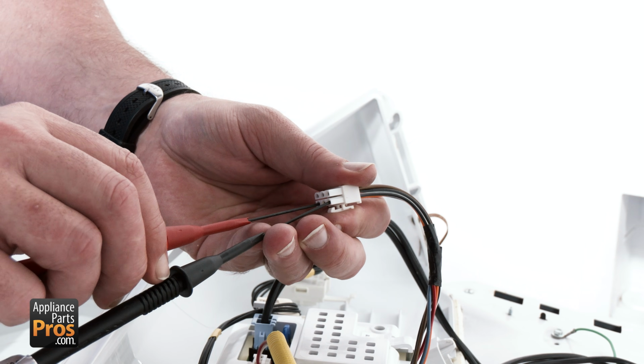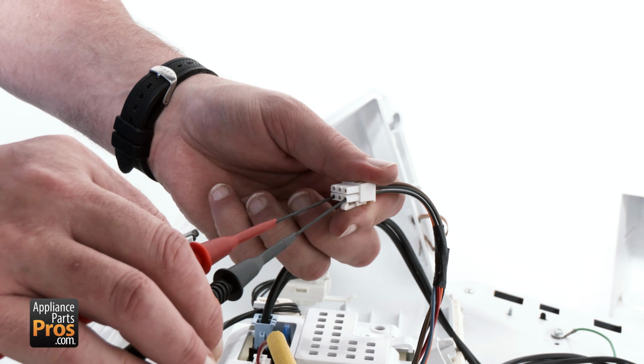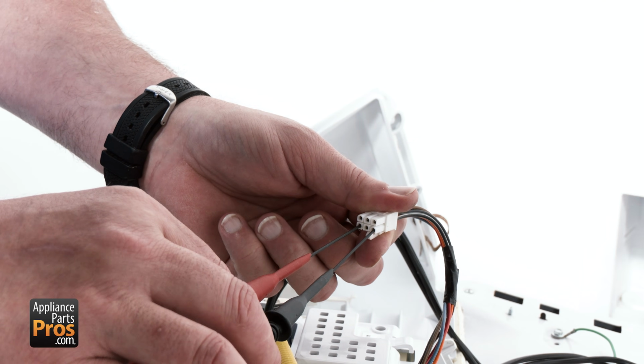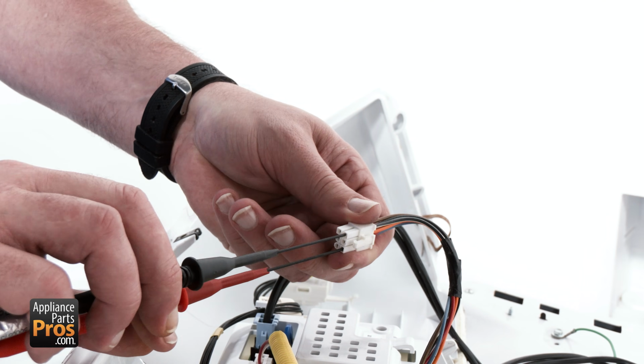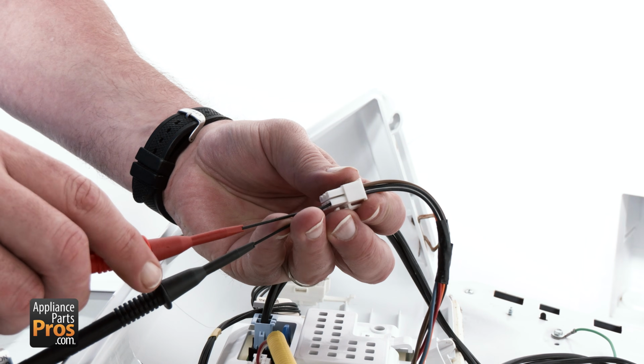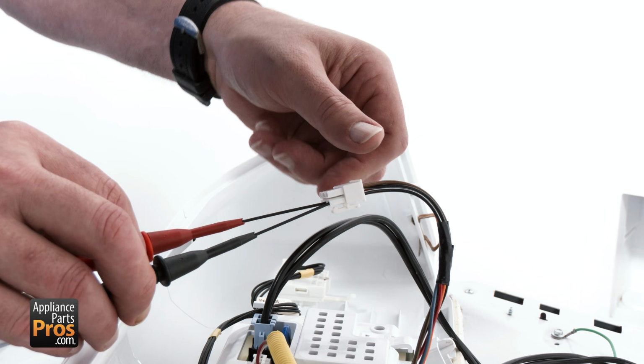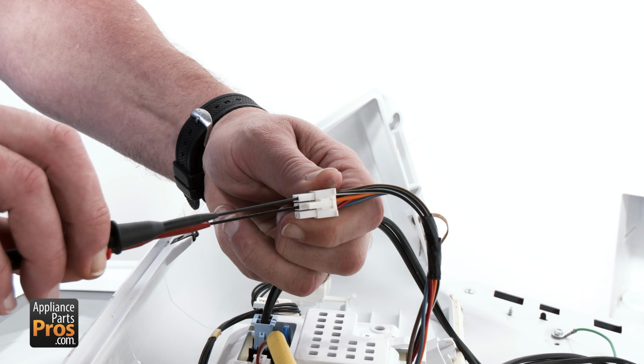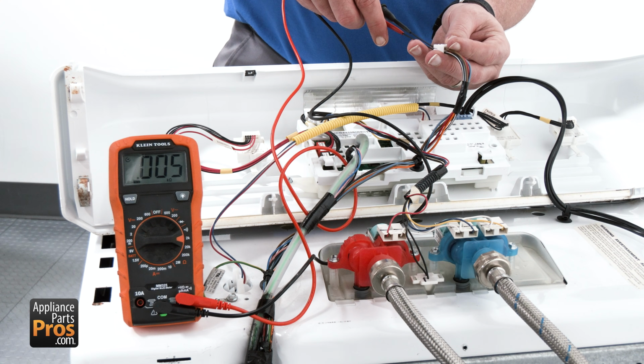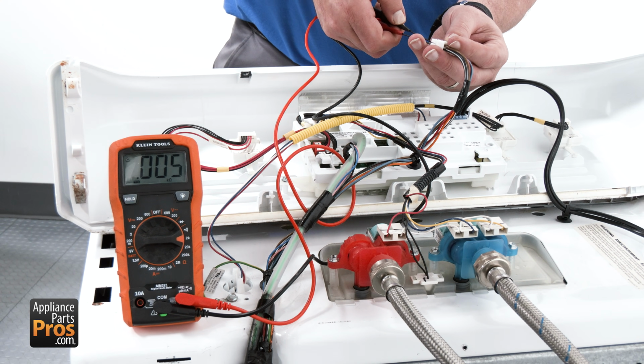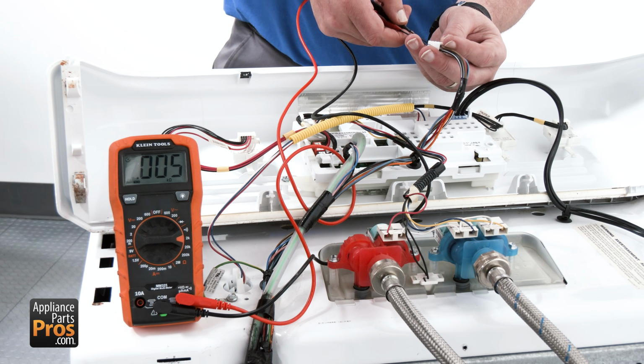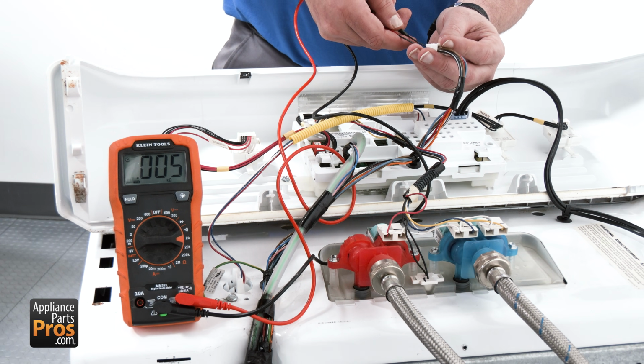Using your multimeter set to ohms, measure resistance between J2 pin 4 and J2 pin 6 for the clockwise winding, then J2 pin 4 and J2 pin 5 for the counterclockwise winding. Each winding should measure between 3 and 6 ohms. In our case, one winding tested open and completely out of specification, confirming the drive motor had failed internally.